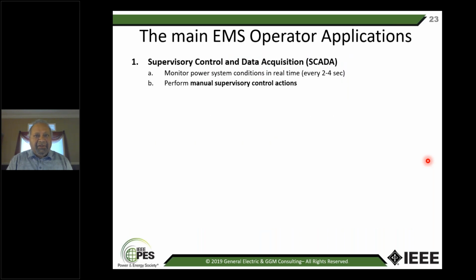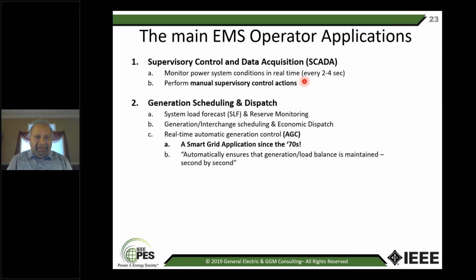The main EMS operator applications: SCADA, which runs every 2 to 4 seconds retrieving data from the grid. You don't know when that measurement was made—it could have been a few seconds or a few minutes ago—but it's brought into the control center every 2 to 4 seconds. SCADA is also the only place where you can perform manual supervisory control actions, like tripping circuit breakers or changing tap settings, done remotely from the control center.